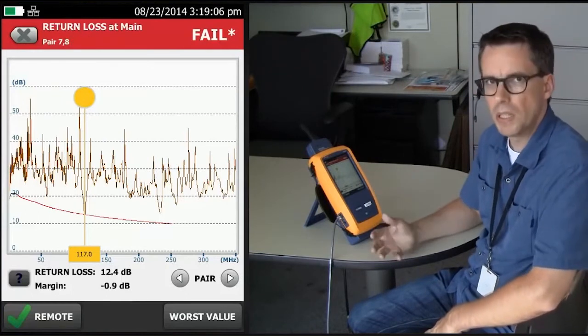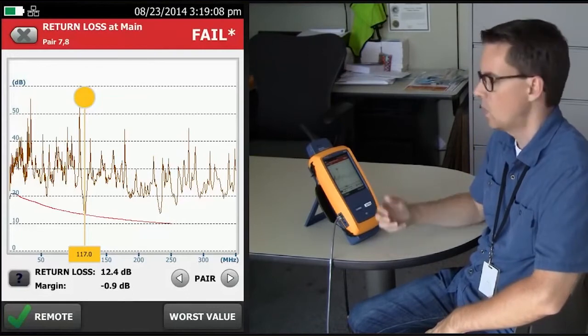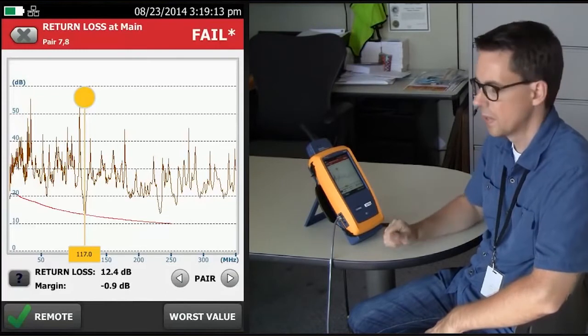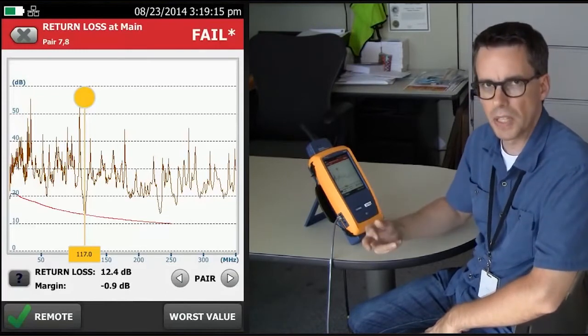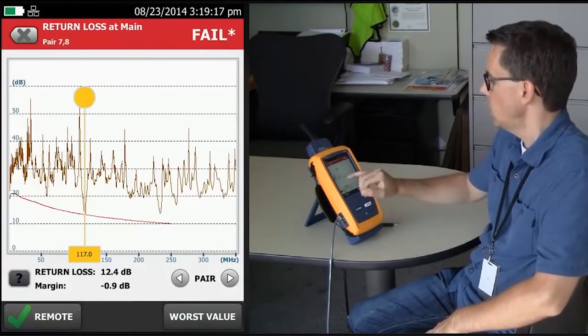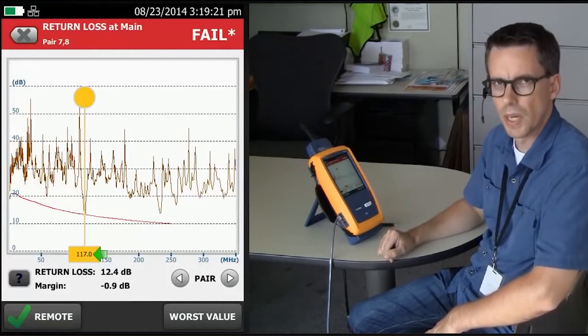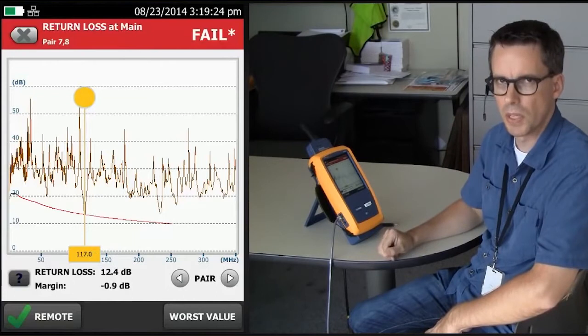Now if you see my DTX videos, you'll know that I say if it fails at the lower end of the frequency range, 50 MHz or less, that tends to indicate a cable issue. When you look at this one here, it's actually failing at 117 MHz, not exactly the low end of the frequency range.